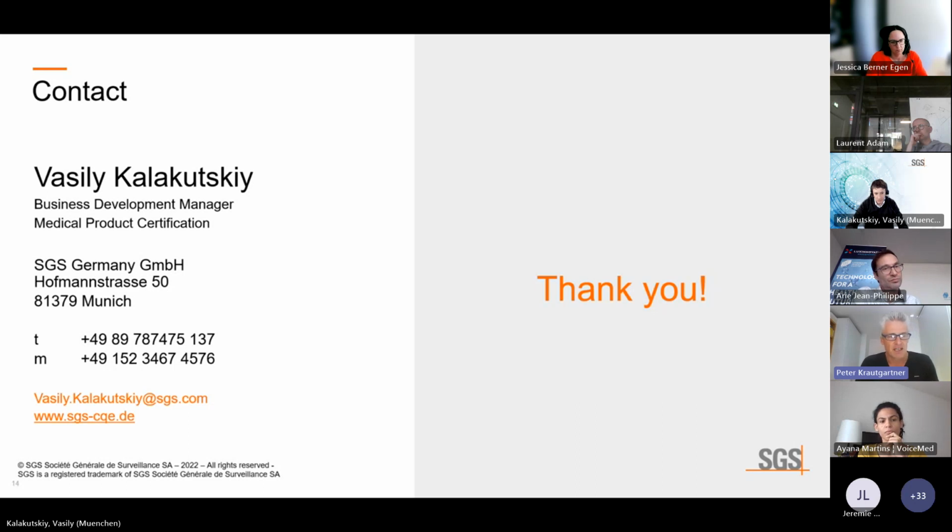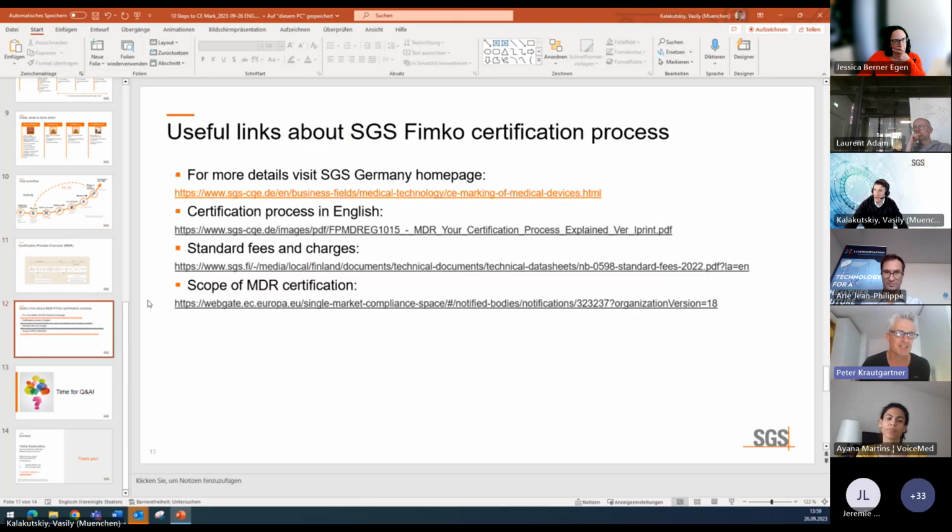My question is because usually this is done with the current routine. You apply for the ISO, and at some point you say, okay, now we are ready to hand in the technical documentation. So as far as I have the experience, it's a parallel process at some point. Do you agree? Did I understand it right? Because this is important for startups to manage carefully this roadmap to certification.